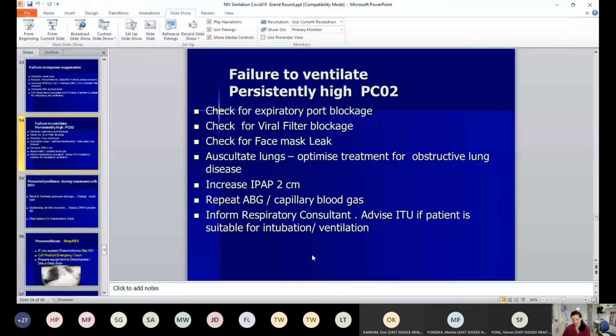Now, if the patient's got a high CO2, for example, if they've got COVID and COPD or just COPD, the steps we'd like you to take is, first of all, put on the full PPE and have a look at them and see whether the expiratory port on the mask is blocked. The nurse should be checking this every hour, so they should be able to have picked up that problem already. Check the viral filter, and that again should be changed every 24 hours, and check for mask leak.